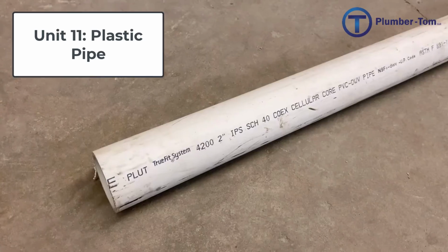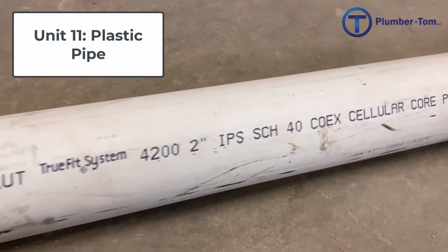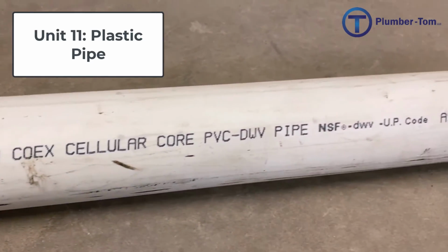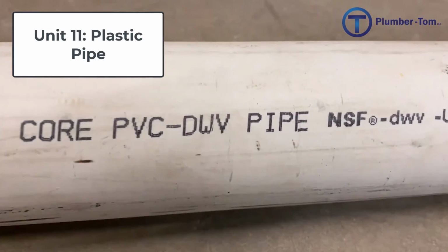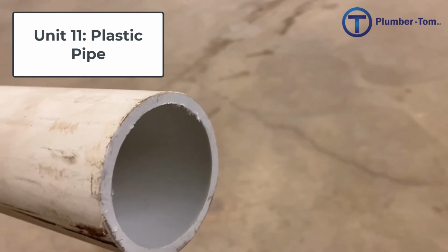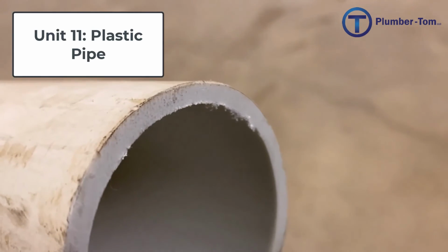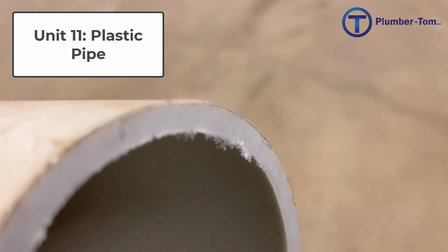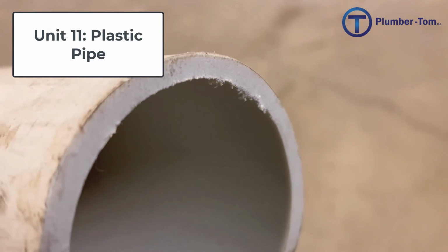As I've mentioned, PVC pipe is good for drainage or water lines, but you need to be aware that when it's drainage and it's listed DWV on the pipe, usually that has the cellular core. It's a more hollow or foam core inside of the pipe wall. It makes it a little more lightweight. It's cheaper to produce, but it is not as strong. So you don't want to be using a DWV pipe for a pressure situation, like putting a PVC DWV in a sprinkler line, it may rupture, or for other applications.